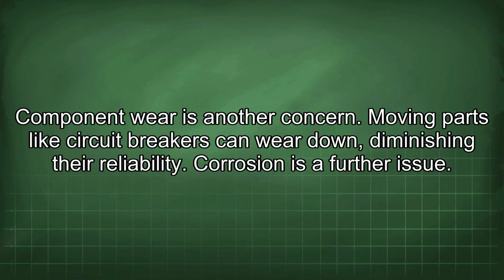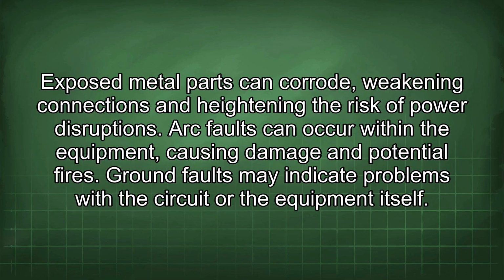Component wear is another concern. Moving parts like circuit breakers can wear down, diminishing their reliability. Corrosion is a further issue. Exposed metal parts can corrode, weakening connections and heightening the risk of power disruptions. Arc faults can occur within the equipment, causing damage and potential fires. Ground faults may indicate problems with the circuit or the equipment itself.